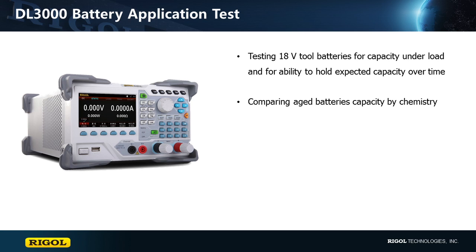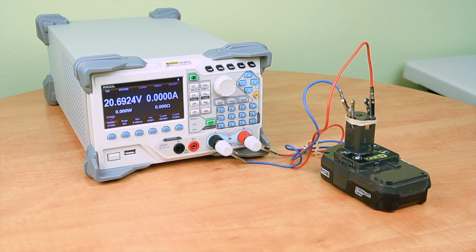Let's take a look at our test setup for one of our 18 volt lithium battery tests. Here we are with our DL3031A electronic load connected to an 18 volt lithium ion tool battery. Let's first take a look at how we're going to set up this battery test.